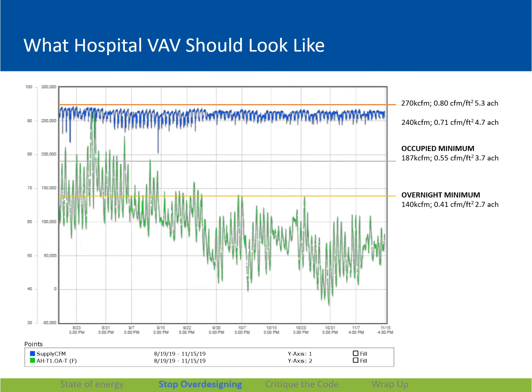The average code minimum at night is significantly less. Some of these spaces can shut completely down. Most of them can turn down. So you should be seeing about 0.4 CFM per square foot, which is more like 2.7 air changes an hour for the volume of your spaces at night. When it's 65 degrees at night, 70 degrees at night, that's where you should be running.